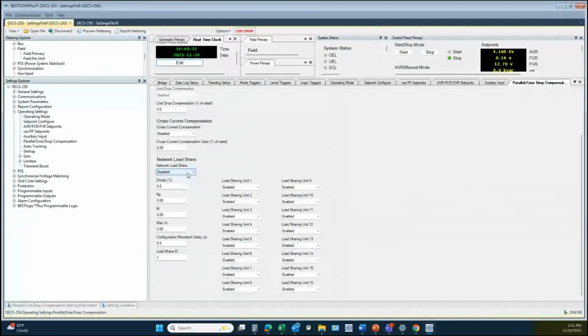You would also set up, if you plan to use the DECS 250 or any of these DECS products, the network load sharing. I don't really have time to go into too much discussion, but the network load sharing allows the units to share reactive power proportionally between the machines on an islanded system. Essentially, it's a modern way to do cross current compensation without all of the cost associated with the extra current transformers and conductors and the headaches of balancing CT burdens between machines that a cross current loop introduces.